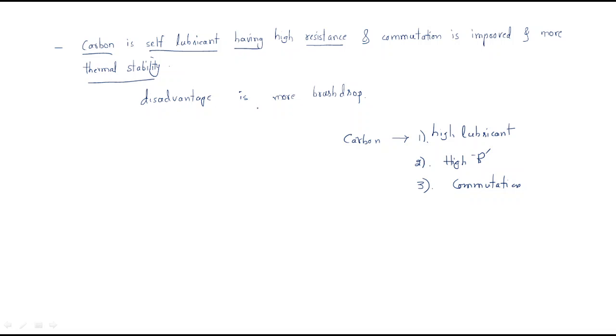The disadvantage of carbon is more voltage drop. Whenever carbon is used, since it has high resistance, the voltage drop will be high. This is the main disadvantage of carbon brushes.